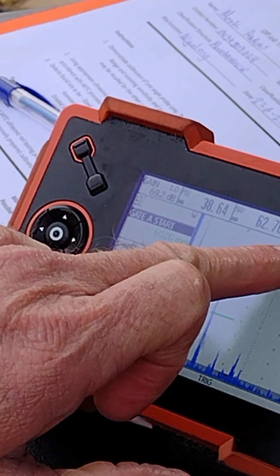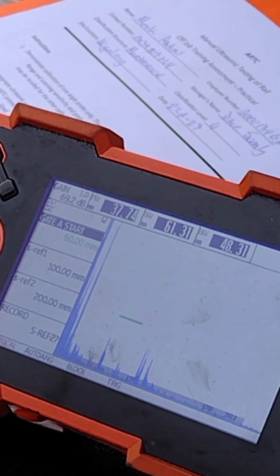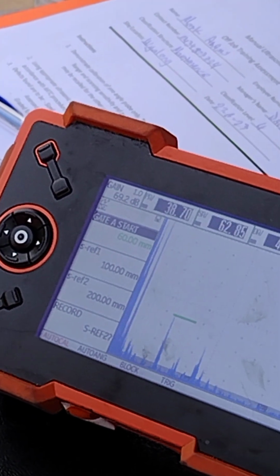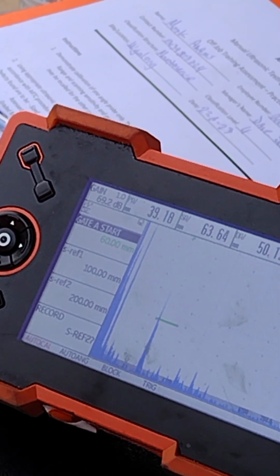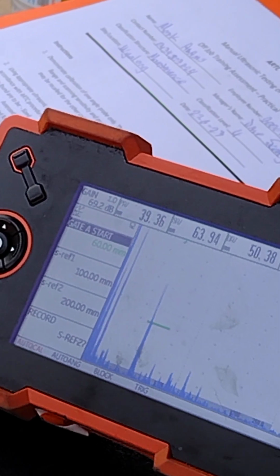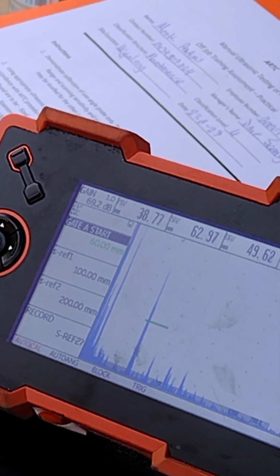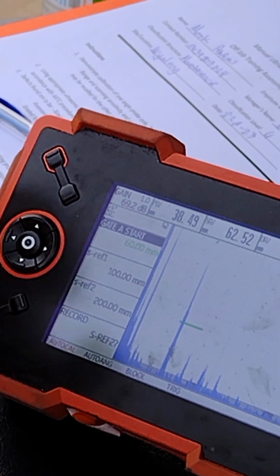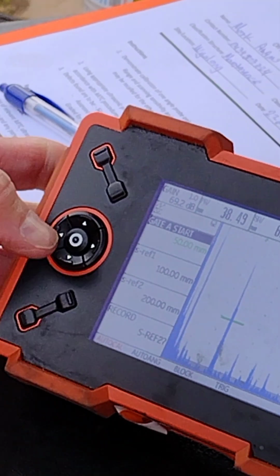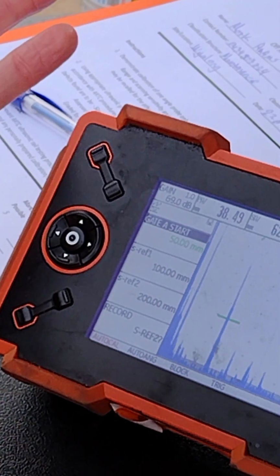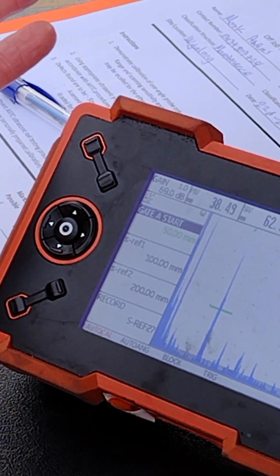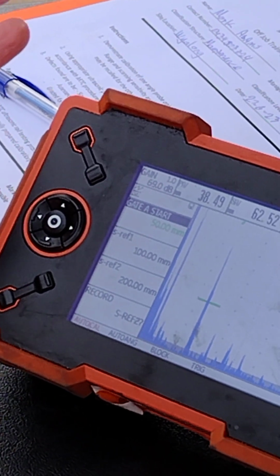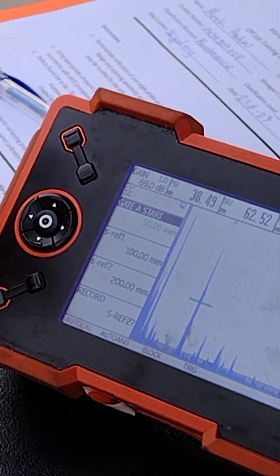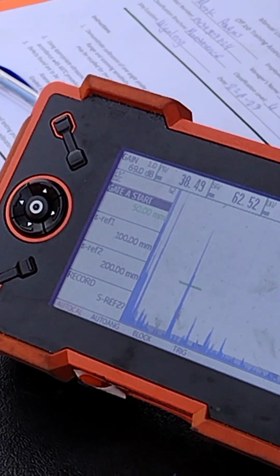There we go, we've got the right peak, it's 49, we're looking for 50-ish. Going to maximize that peak by swiveling our probe, moving it backwards and forwards, and then once we get it maxed out, we'll auto 80, and we've now got evaluation sensitivity. We'd add 6 dB for scanning. Job done.